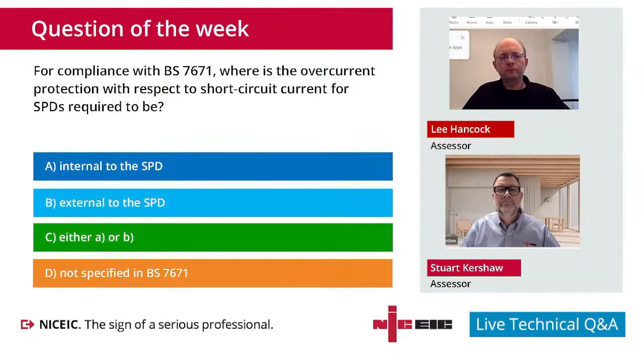So without any more ado, we'll have a look at the question of the week that we posted out on Monday. And Monday's question was regarding SPDs. The question was, for compliance with BS 7671, where is the overcurrent protection with respect to short circuit current for SPDs required to be? Does it have to A, be internal to the SPD? Does it have to B, be external to the SPD? Can it C, be either internal or external? Or D, is that not specified in 7671?